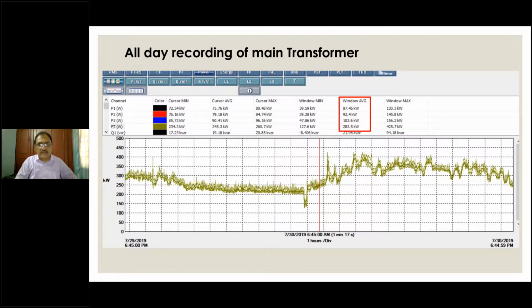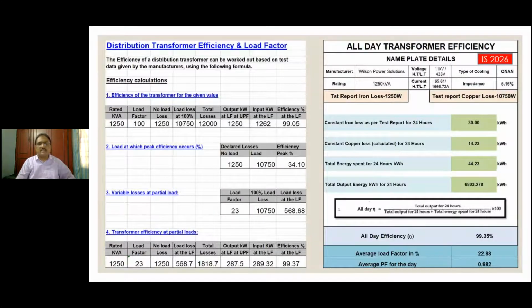Remember, it is a 1250 kVA transformer. So with only 283 kilowatt, the load factor is less than 25%. They have probably purchased this transformer for future expansions and things like that. It is an oil cooled transformer, I know it for a fact. So what does this information give us? This is only a 23% load factor, as you can see here. Based on this Excel calculation, we can find out the efficiency of the transformer.